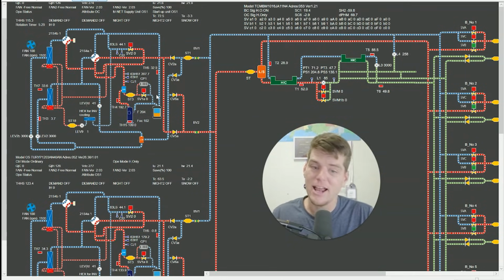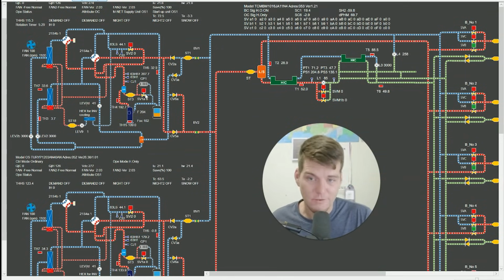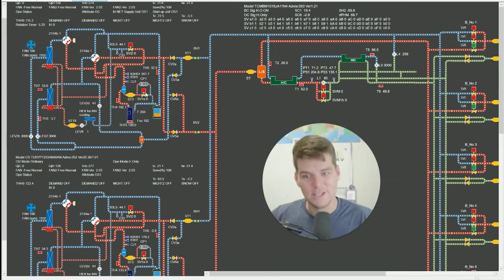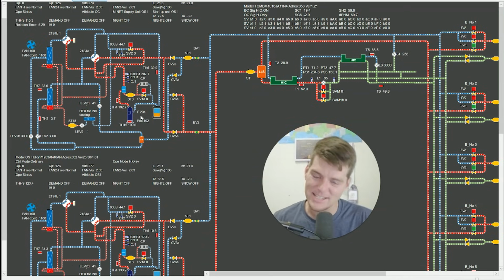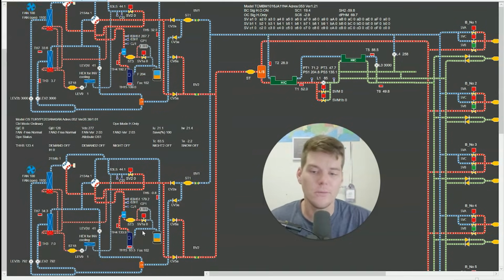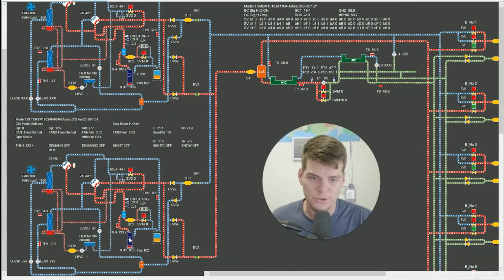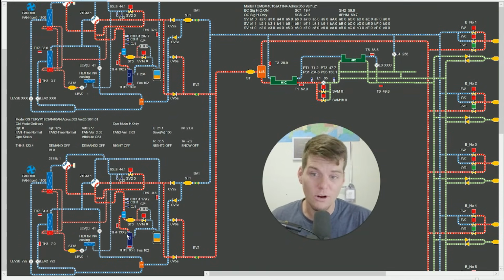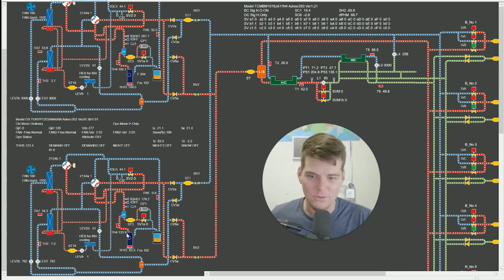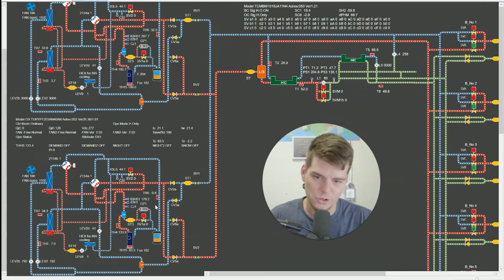High discharge superheat, high suction superheat. It's not getting enough refrigerant. I'm not saying it's low charge, just saying this compressor specifically is not getting enough refrigerant. What about my other compressor? Well, the other compressor is low discharge superheat, right? And I would say low, maybe it's in the 50 range, but it's still lower drastically than our master module. So then let's look at what's the suction superheat.